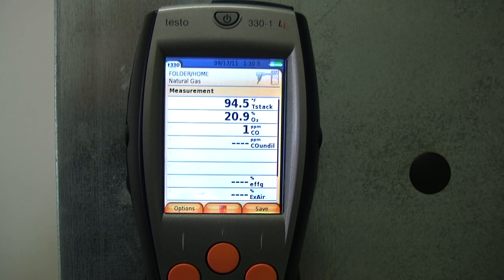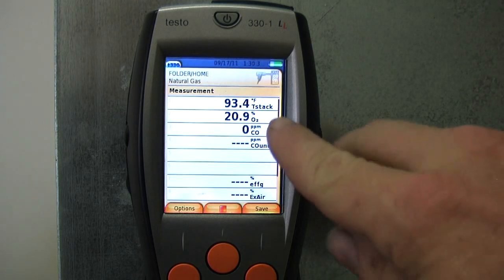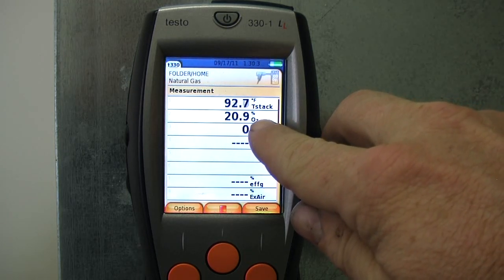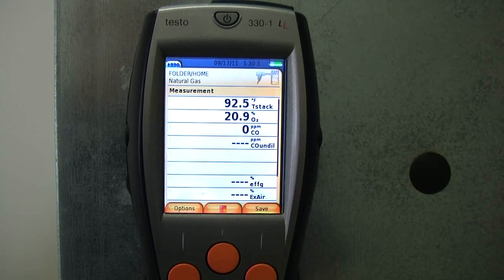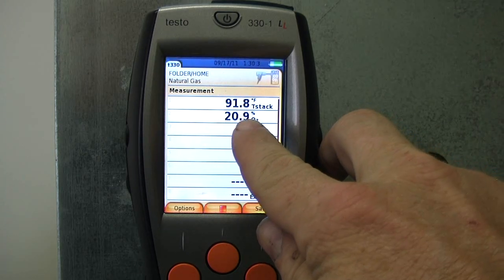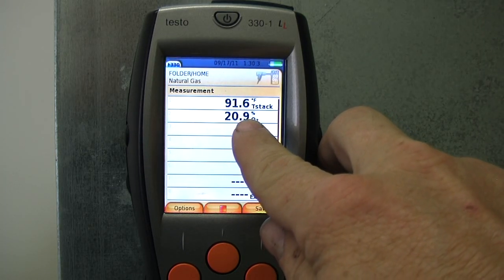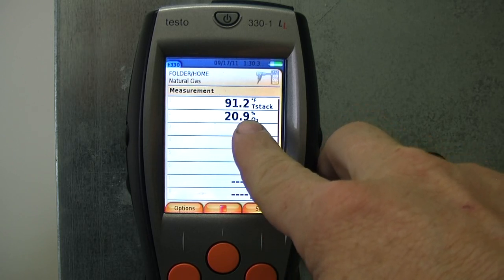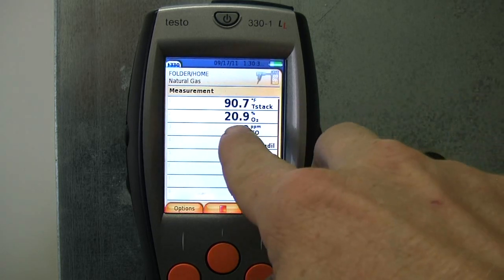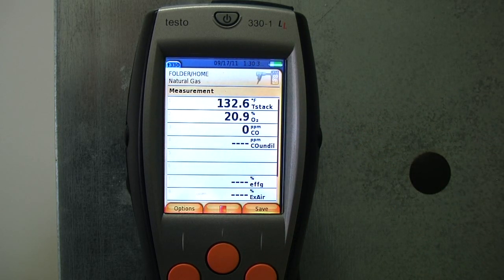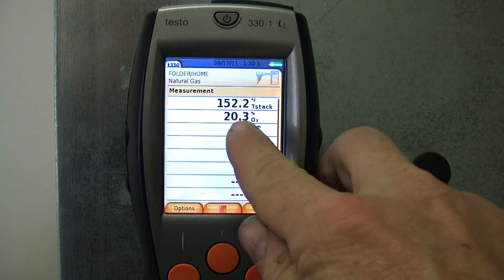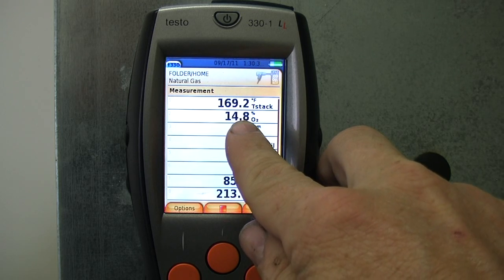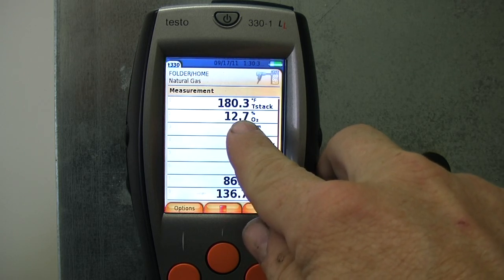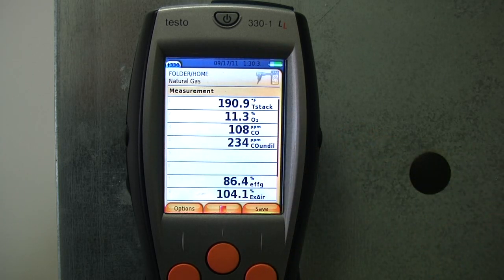Alright, so what's going to happen is we're going to go ahead and get the burners going. We're going to watch O2, which is oxygen. There's 20.9% oxygen in air. Alright, so when the burners fire off, we're going to watch this number and it's going to drop. Most of the time it'll drop down to about 10, 9, 7 down in that area. Now, after it drops, the blower is going to kick on. Now, when the blower kicks on, if this number raises any at all, that's telling you that more oxygen is being reintroduced to the combustion. Right, there's nothing inside the furnace that's going to produce oxygen, except for the blower when it kicks on.